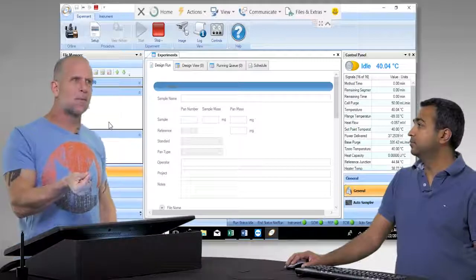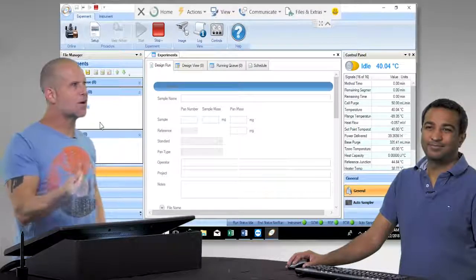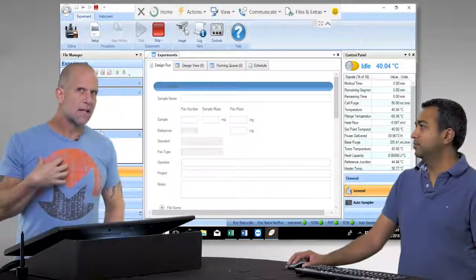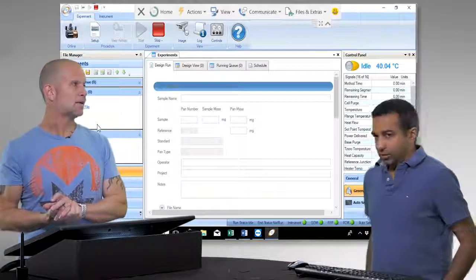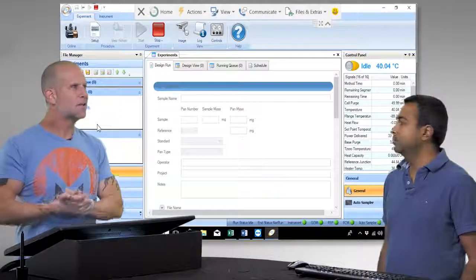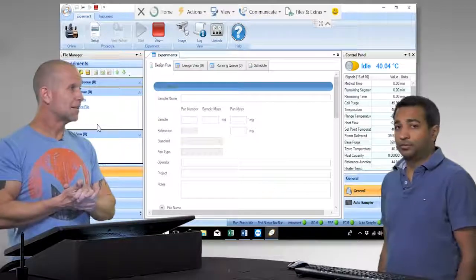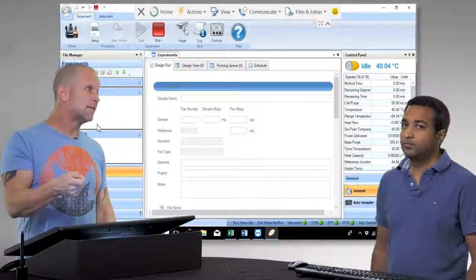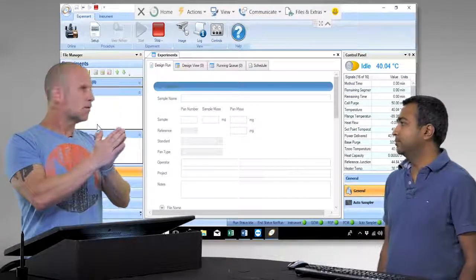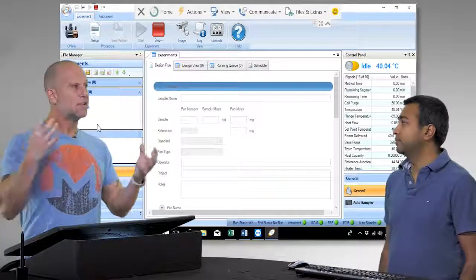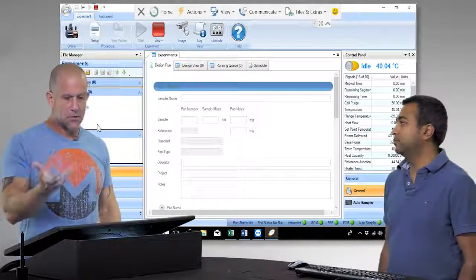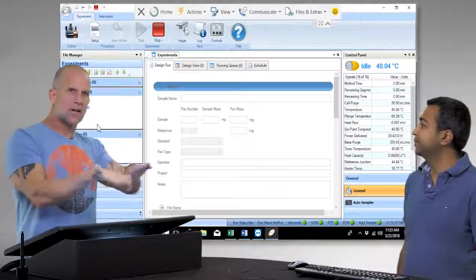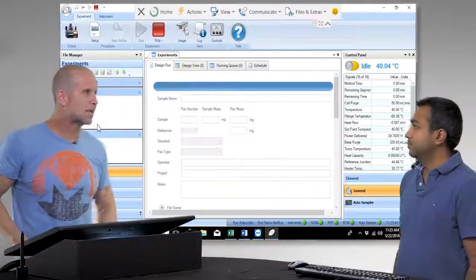Indium is the most commonly used standard for differential scanning calorimetry. It's in a somewhat accessible temperature range — between 100 and 200 degrees Celsius. You need a metal that doesn't oxidize easily, and being a metal means it won't have much vapor pressure or change. It just has a lot of characteristics that make it really good for using the melting point as a standardization that lasts a long time. Metals are very good thermal conductors, which makes a big difference.